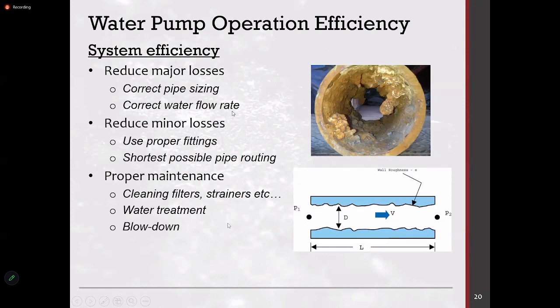Okay. And the water flow rate. Generally we design pipes to have 1 meter per second water flow rate. But lower than that is also better so that you have less friction. So the lower the diameter, the higher the friction. And the other thing is proper fittings. Now, you may have heard of plumbers being very reluctant to use 90-degree elbows. Sometimes they use 45-degree bends, or they use bends. Bends are a gradual circular turn, which doesn't happen at 90 degrees. It's not an elbow. So that will reduce the pressure loss and the pump head.